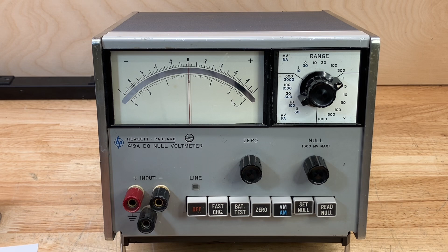That was very useful for Cal labs back in the 1960s because they used to use these to compare their reference voltages to a Weston standard cell, which is a battery, a special chemical battery that produces a precise 1.01830 volts. Exactly 1.01830 volts, but it can only produce that precise voltage when you are not drawing any current from that battery whatsoever. If you draw even a small amount of current from that battery, the voltage will no longer be accurate. And if you draw more than a small amount of current from that battery, such as a microamp or more, you in fact will damage the battery, and it will be permanently destroyed.